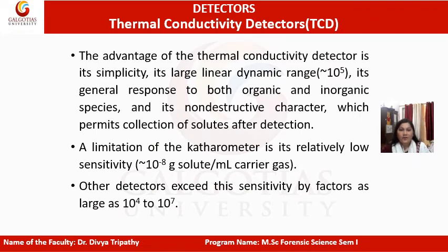The advantage of the thermal conductivity detector is its simplicity, its large linear dynamic range, its general response to both organic and inorganic species, and its non-destructive character, which permits collection of solutes after detection. A limitation of the katharometer is its relatively low sensitivity. Other detectors exceed this sensitivity by factors as large as 10 to the power 4 to 10 to the power 7.